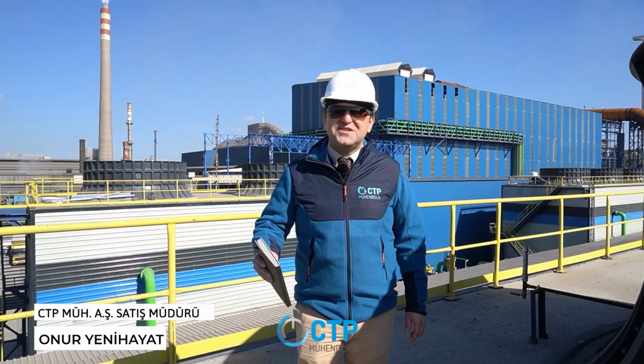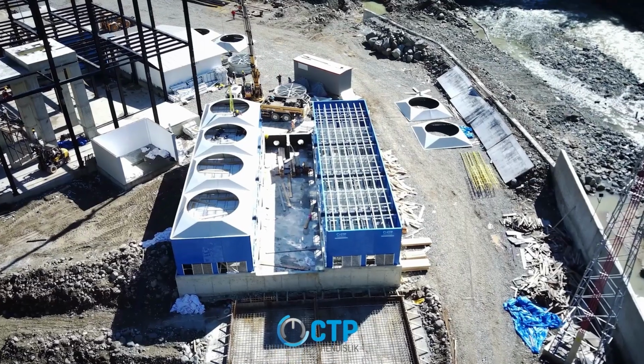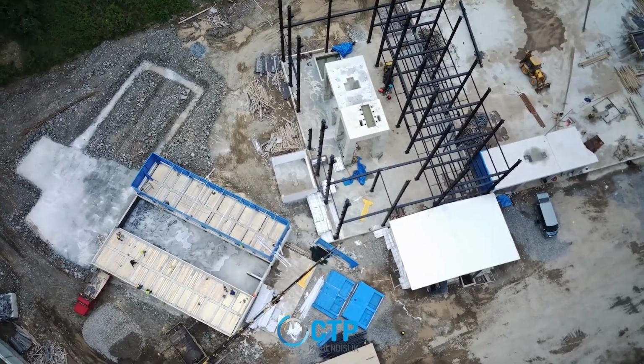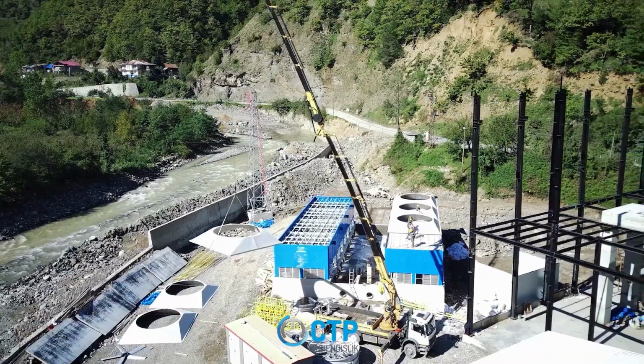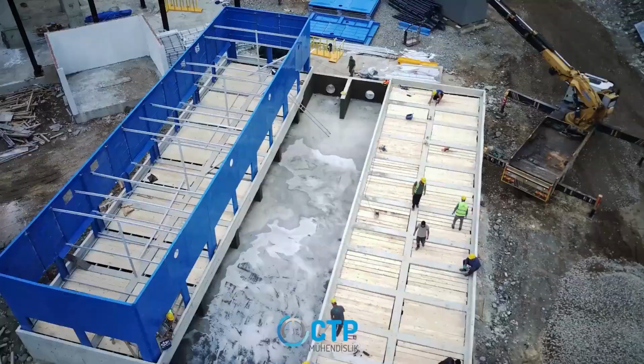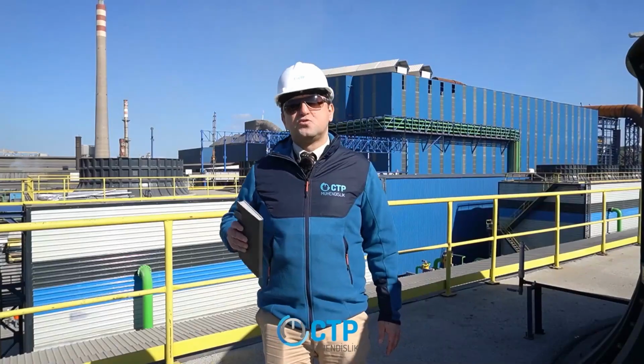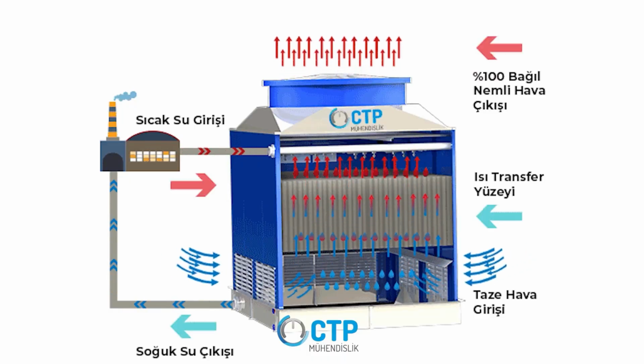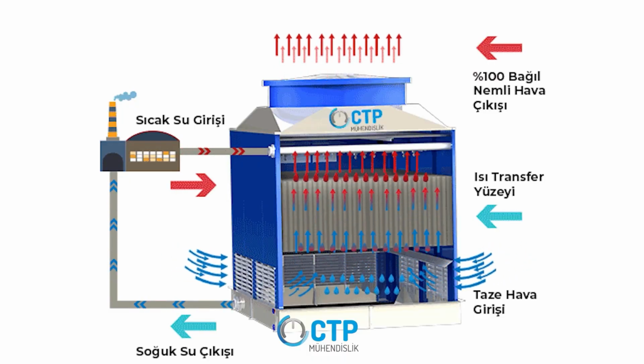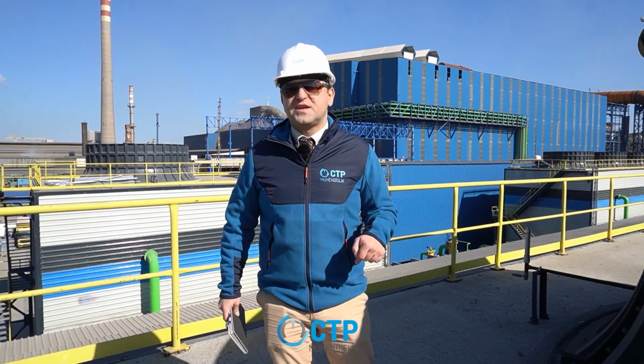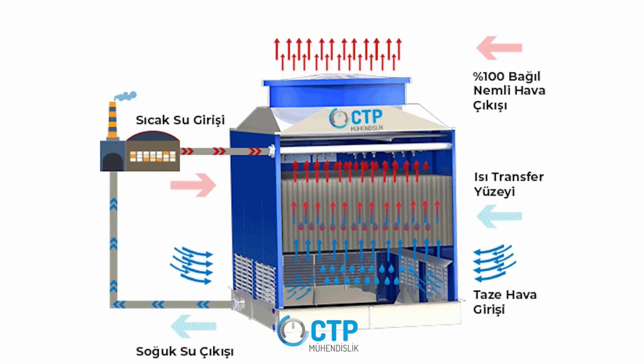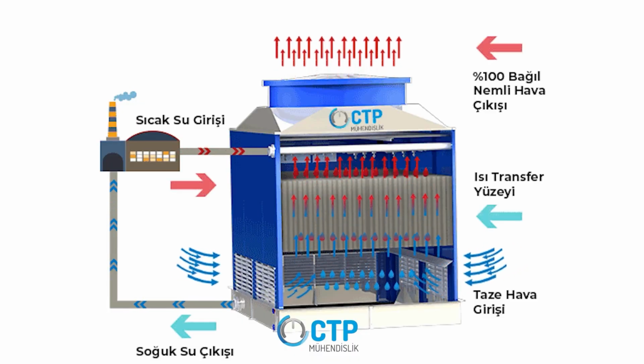As the name suggests, a cooling tower is a device that performs cooling. This could be in a process involving machines or presses. It could be the ladles of a rolling mill. Something operates and generates heat. That heat is collected in the water. The water is sent to the cooling tower. In the cooling tower, it is cooled, brought back to its initial temperature, and then returned to the machine or equipment in the process, whatever that may be.